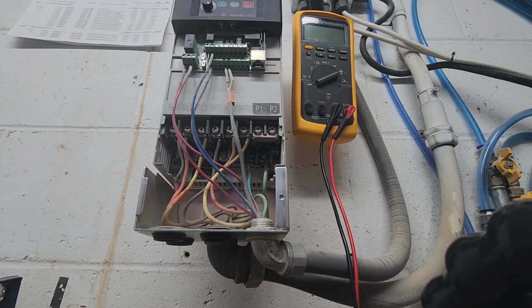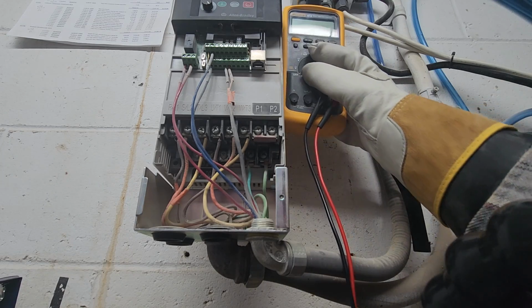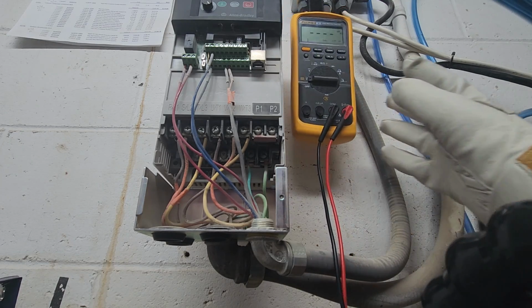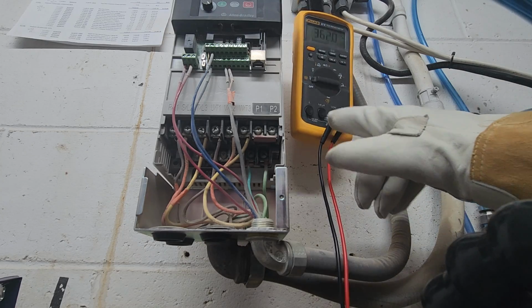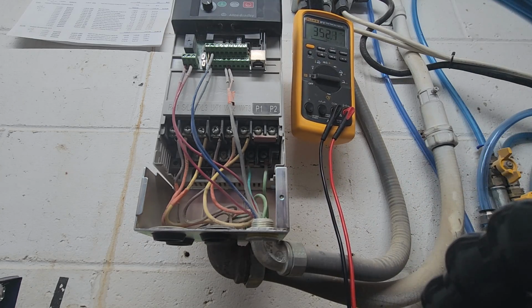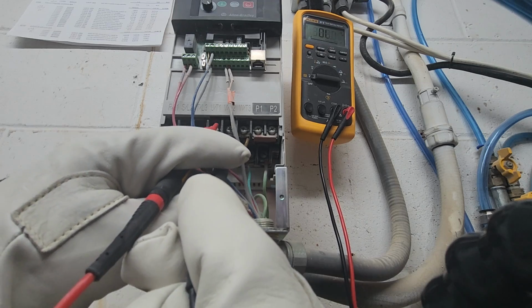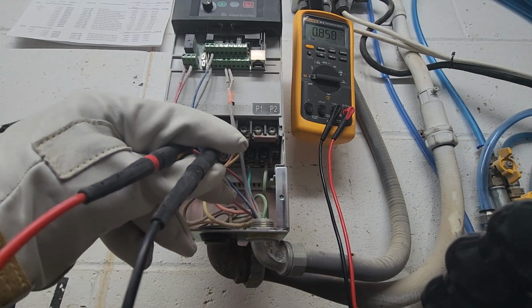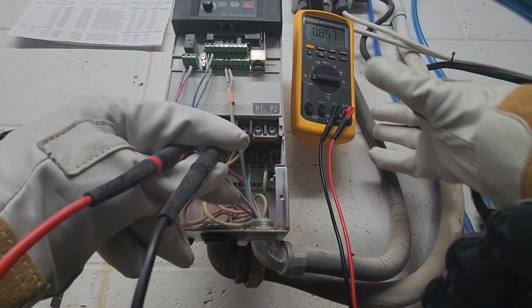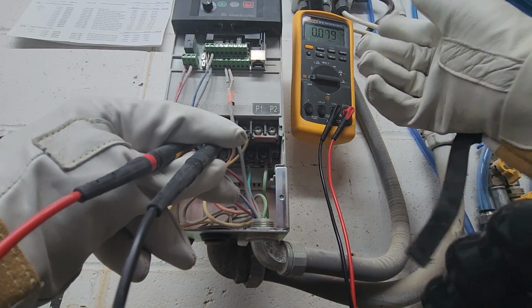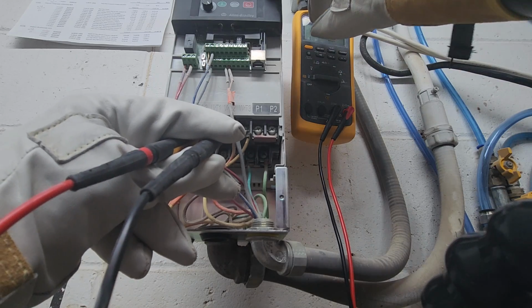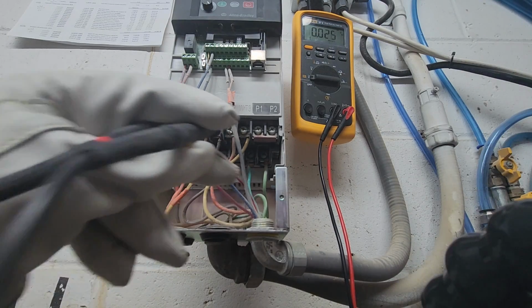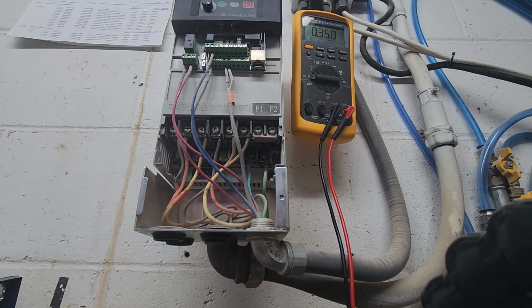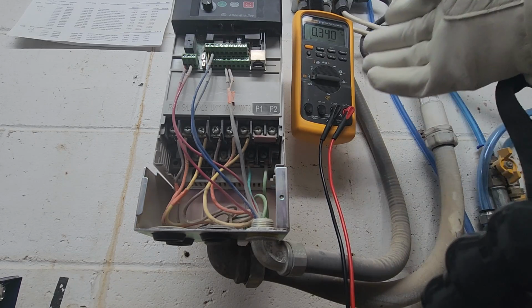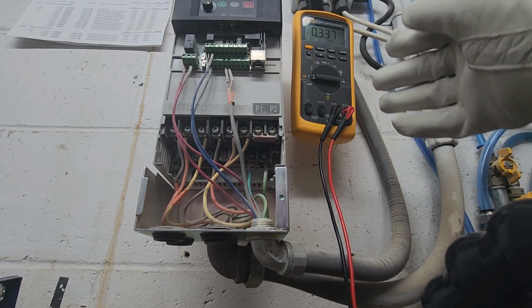Again, peak voltage. So the next thing you can do for checking is turn your meter to volts. On the 87-V, we'll put our terminal 1 to terminal 2 and check our voltage output. Now we need to use our low pass filter for this. So we engage our low pass filter. If this VFD up here said it was running at 240 volts, we should see 240 volts on our multimeter with the low pass filter engaged.